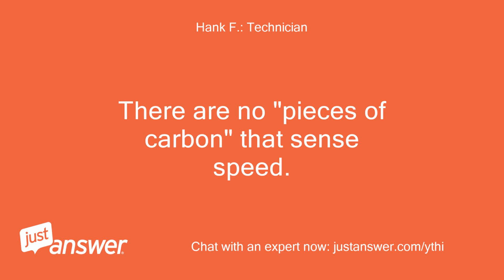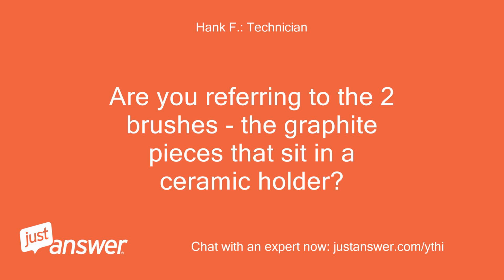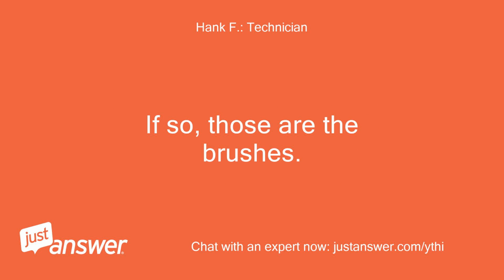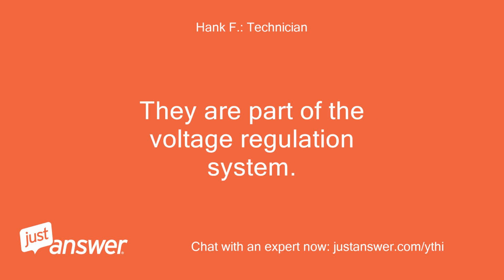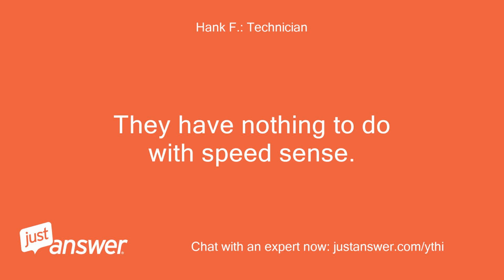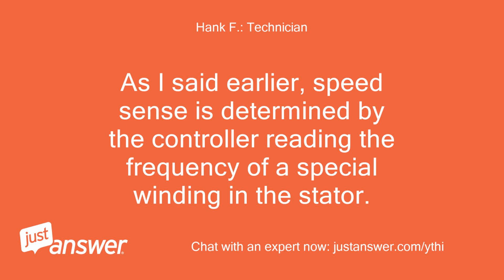There are no pieces of carbon that sense speed. Are you referring to the 2 brushes, the graphite pieces that sit in a ceramic holder? If so, those are the brushes. They are part of the voltage regulation system. They have nothing to do with speed sense. As I said earlier, speed sense is determined by the controller reading the frequency of a special winding in the stator.